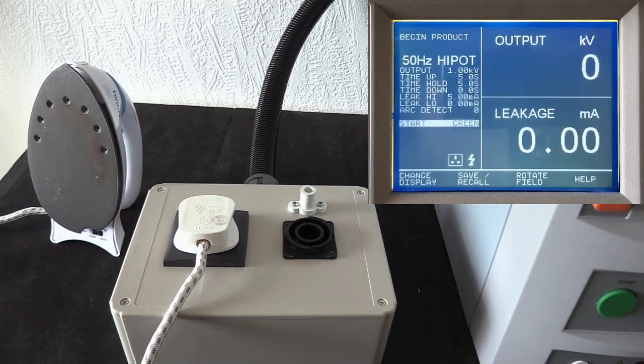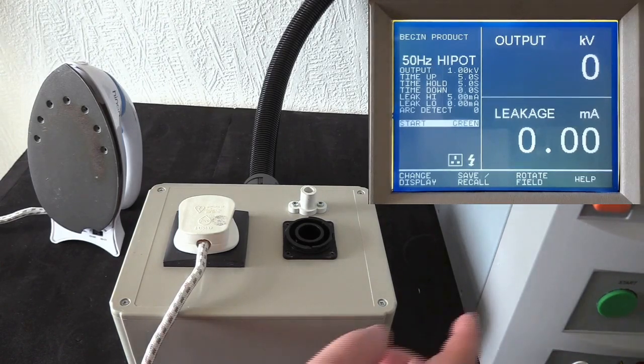Okay, so let's now start the test off. You'll notice we're performing the test at 1000 volts. We're going to raise that voltage over 5 seconds. We're going to hold it for 5 seconds, which is typically longer than a normal production line, which may only take a couple of seconds to perform. We've got a limit of 5 milliamps, so providing the leakage is less than 5 milliamps, the test will pass. Let's go ahead and start the test and see what happens.